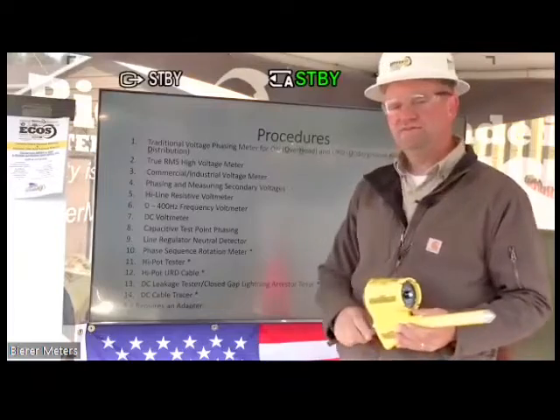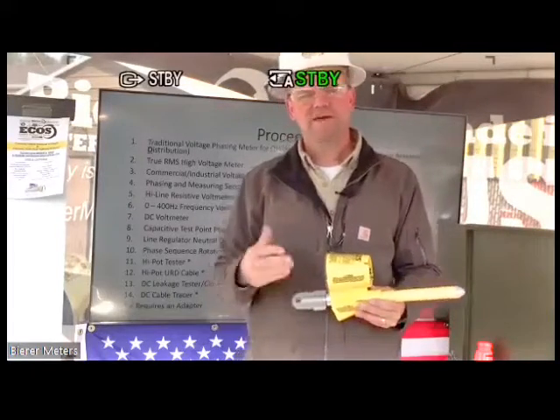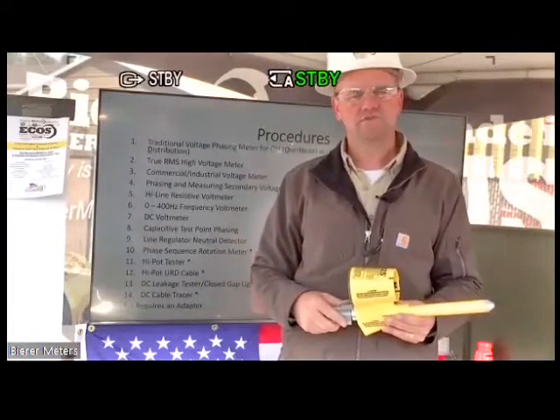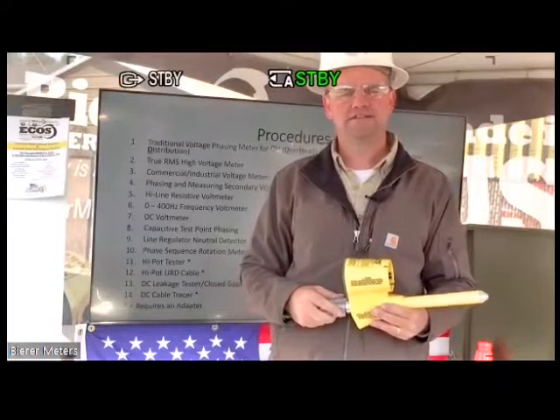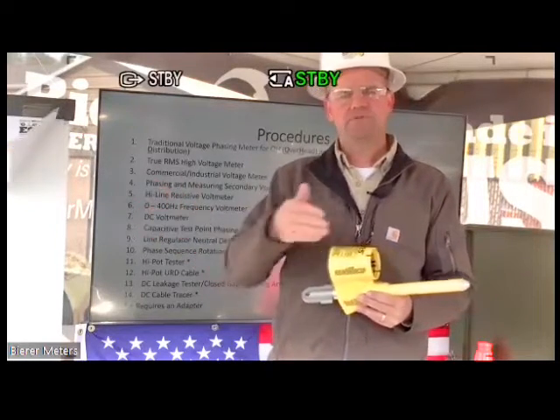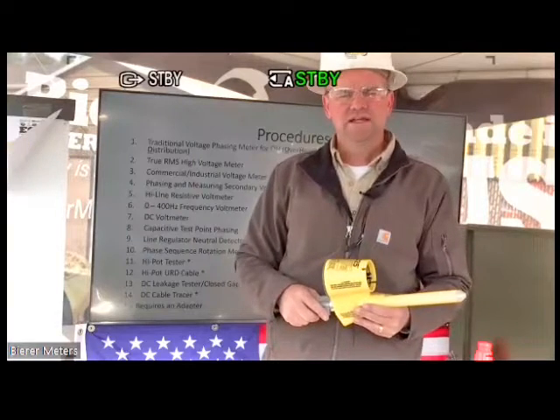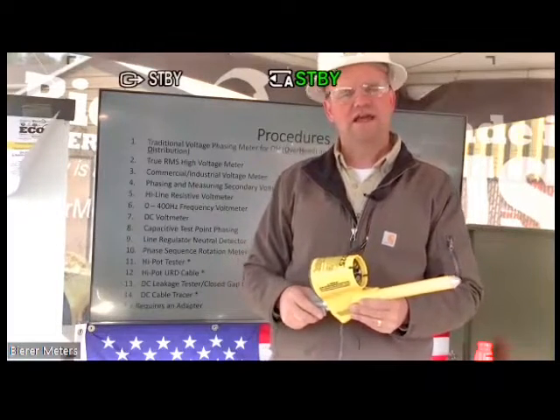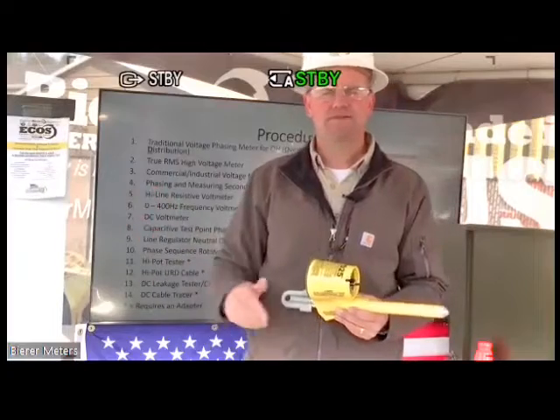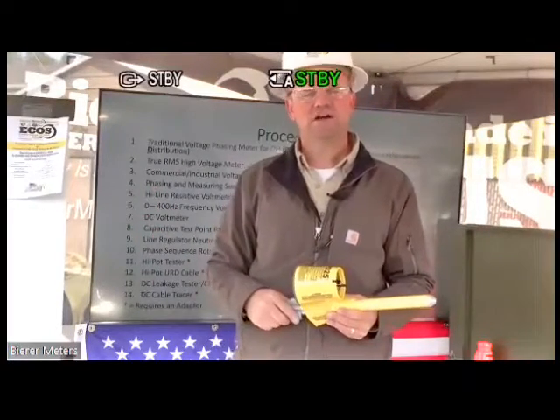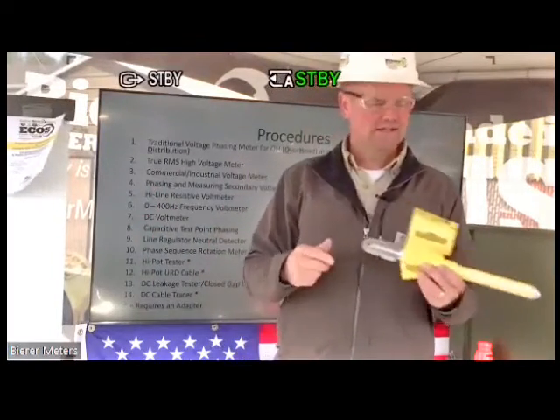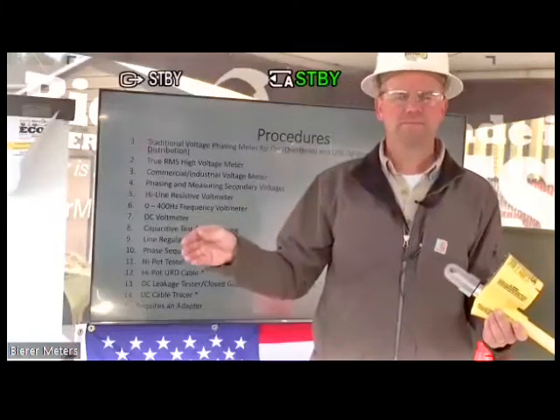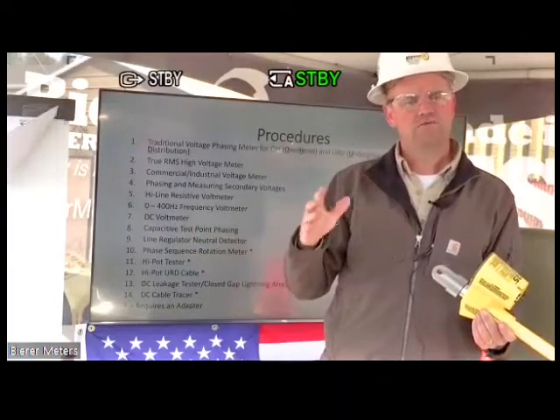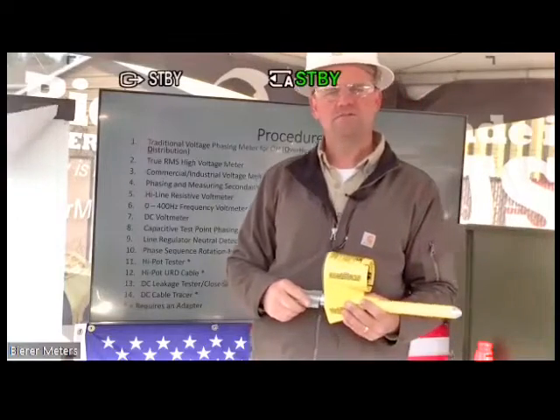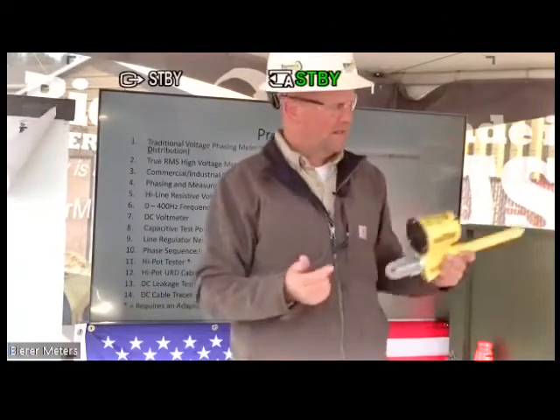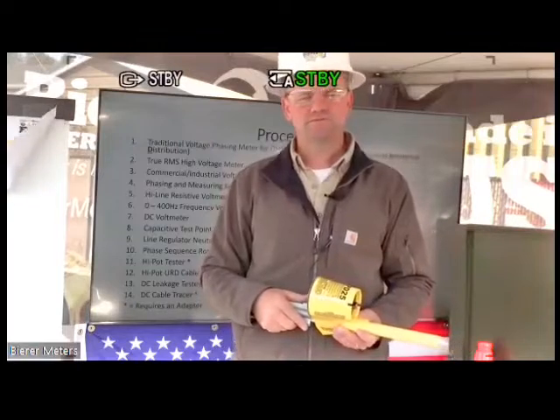A high pot tester. This tool can be used to high pot primary cables. A lot of times traditional phasing meters are used in that capacity. You just have a high pot adapter you thread on the end of this tool. What's nice about this tool, again with the accuracy, is I can actually test the high pot. That's a single-use device with a lot of manufacturers. I can test the high pot phase to ground, make sure the high pot is working. You should get roughly 70% of your phase to ground potential on your display. And then I can high pot that primary cable.